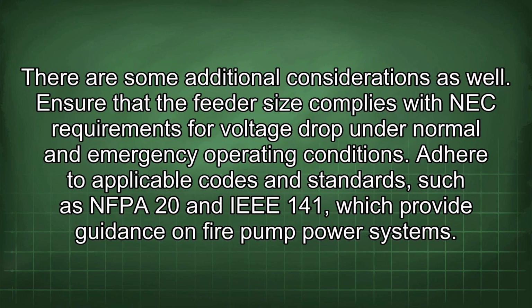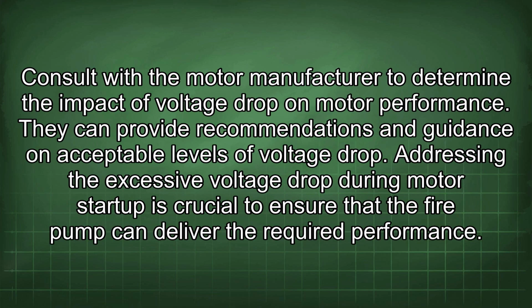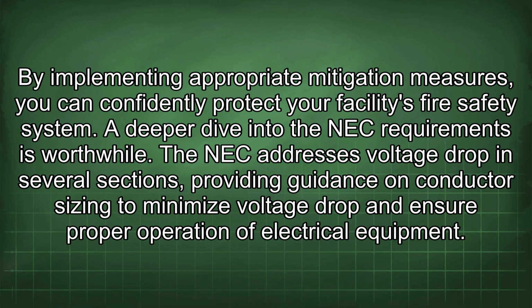There are some additional considerations as well. Ensure that the feeder size complies with NEC requirements for voltage drop under normal and emergency operating conditions. Adhere to applicable codes and standards such as NFPA 20 and IEEE 141, which provide guidance on fire pump power systems. Consult with the motor manufacturer to determine the impact of voltage drop on motor performance. They can provide recommendations and guidance on acceptable levels of voltage drop. Addressing the excessive voltage drop during motor startup is crucial to ensure that the fire pump can deliver the required performance. By implementing appropriate mitigation measures, you can confidently protect your facility's fire safety system.